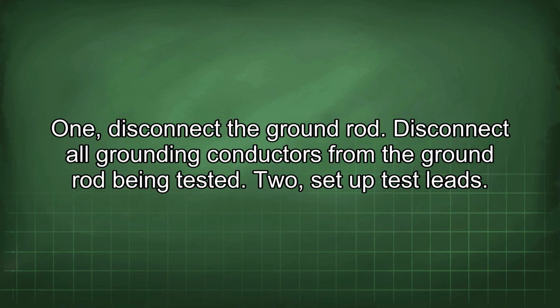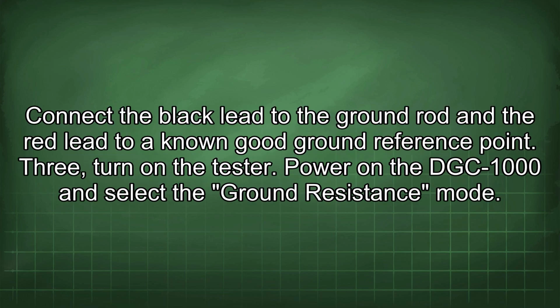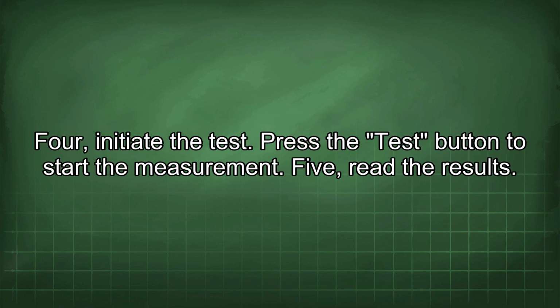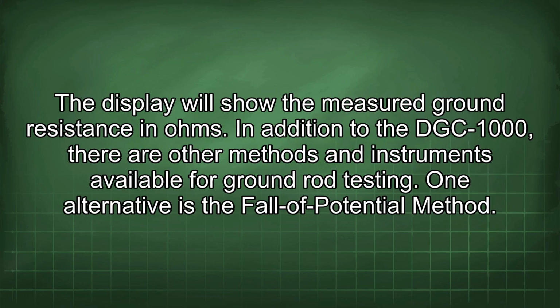1. Disconnect the ground rod. Disconnect all grounding conductors from the ground rod being tested. 2. Set up test leads. Connect the black lead to the ground rod and the red lead to a known good ground reference point. 3. Turn on the tester. Power on the DGC-1000 and select the ground resistance mode. 4. Initiate the test. Press the test button to start the measurement. 5. Read the results. The display will show the measured ground resistance in ohms.